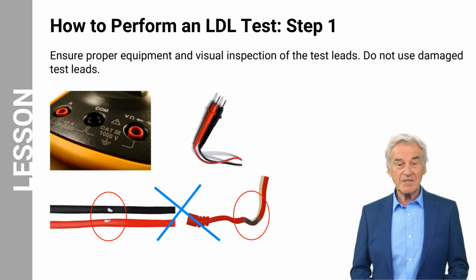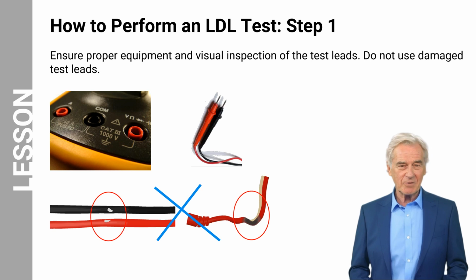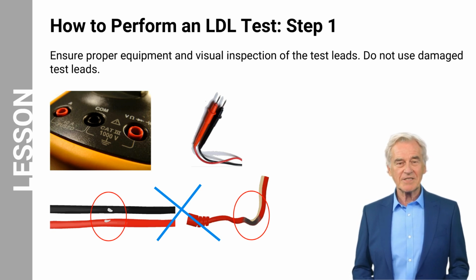Step 1. Ensure the use of proper equipment. Use a Cat 3 1000 volt rated DMM and appropriate lead cables designed for working on HV systems. Do a thorough visual inspection of the lead cables and do not use damaged test leads. Follow all necessary safety protocols, including wearing appropriate personal protective equipment and ensuring the DMM is in good working condition.